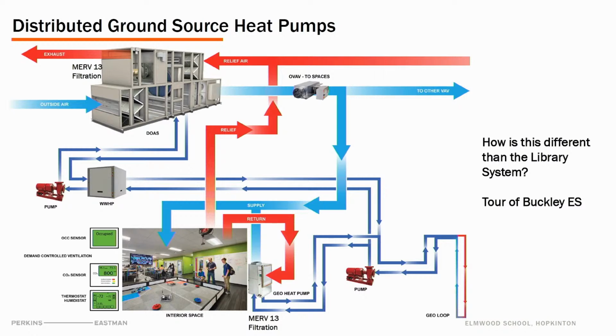So the library system came up. Those familiar with it know the library has a ground source system, but it's what's called an open loop ground source system, which is different from what we're proposing here. We went through the pros and cons, and we're not proposing an open loop, which does have issues that come with it. This is a totally closed loop system, so we're not as worried about the quality of the water coming out of the ground, because the water is contained within the system. We still have to treat the water, but we're not worried about what might come in and out of the ground—that helps that issue go away.